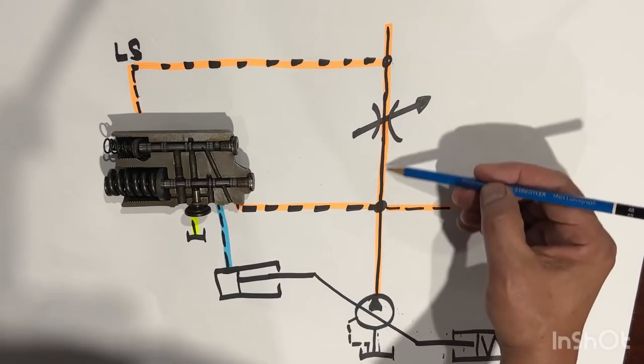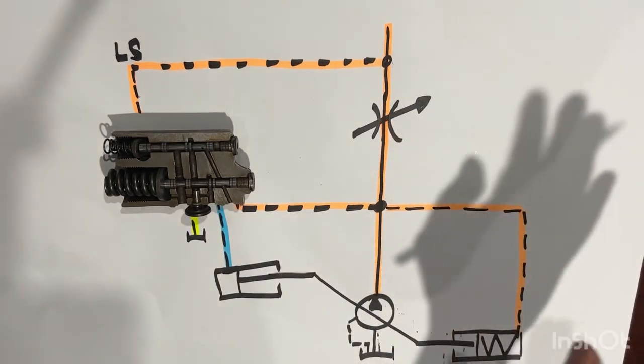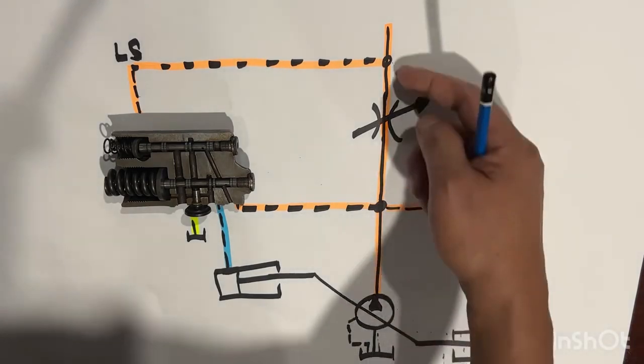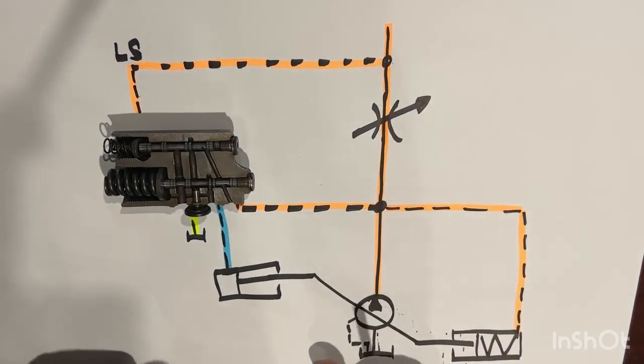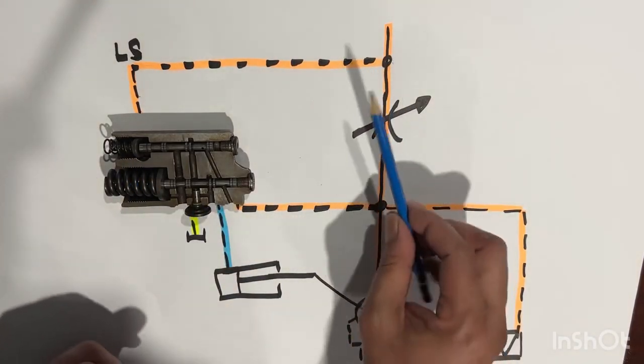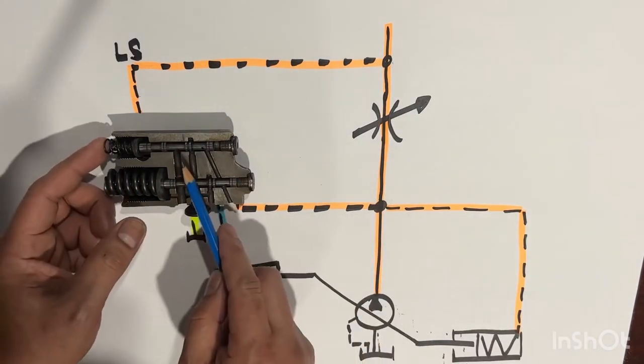Of course, the flow rate here will slowly decrease, and then the delta P will also slowly decrease, until the pump flow across the throttle generates the delta P determined by the FR spool. Until such time, the delta P will become 15 bar, then it goes into balance.